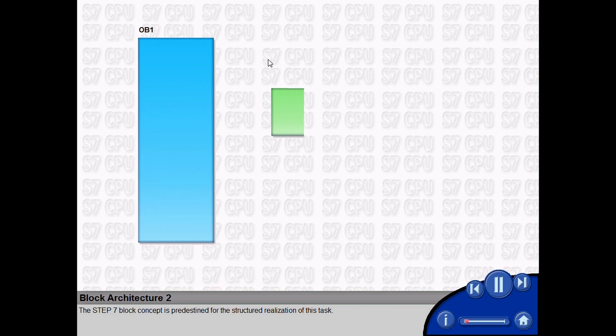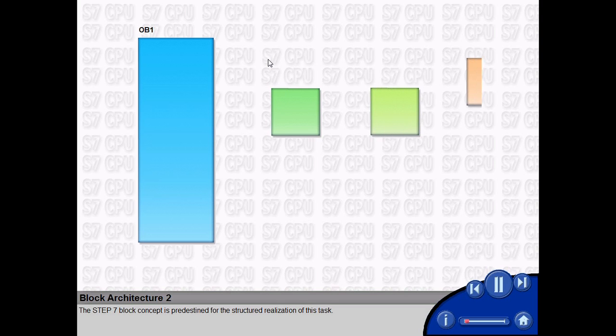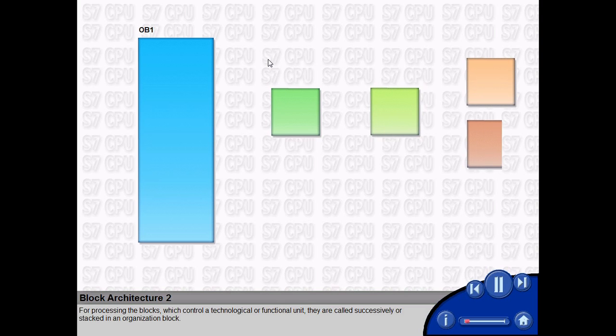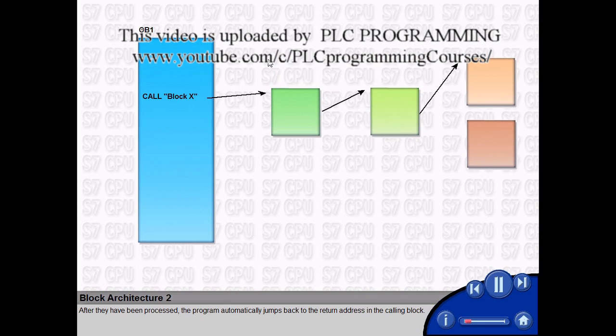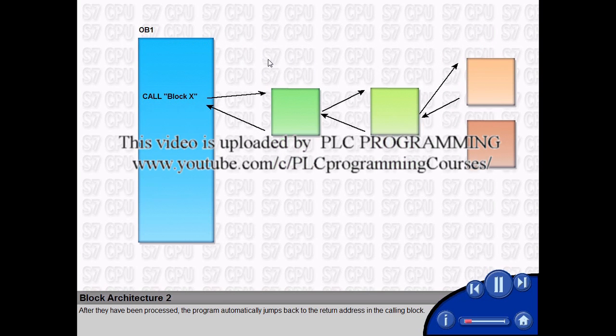The Step 7 block concept is predestined for the structured realization of this task. For processing the blocks, which control a technological or functional unit, they are called successively or stacked in an organization block. After they have been processed, the program automatically jumps back to the return address in the calling block.